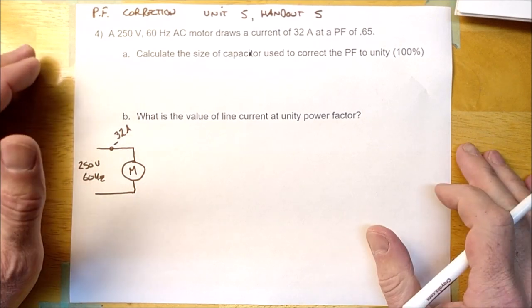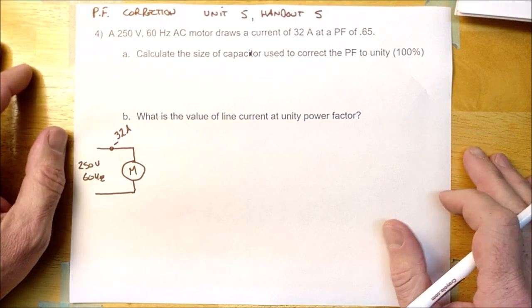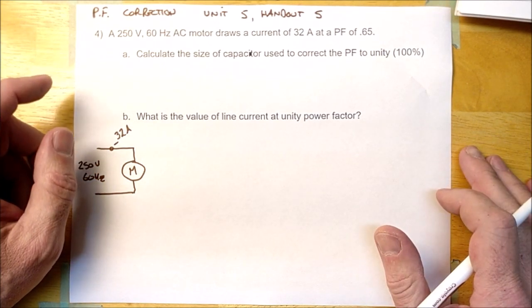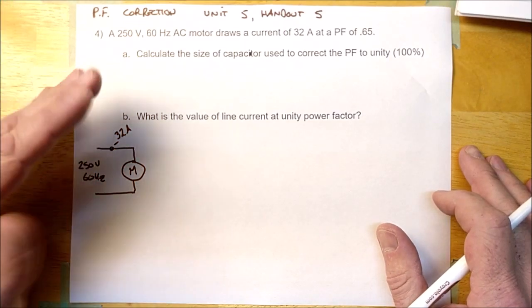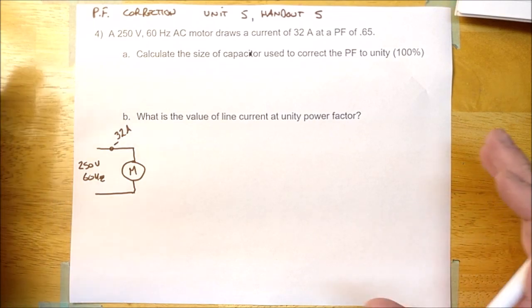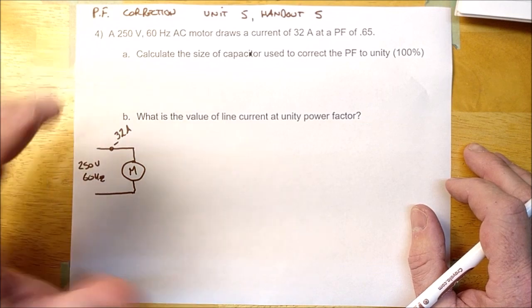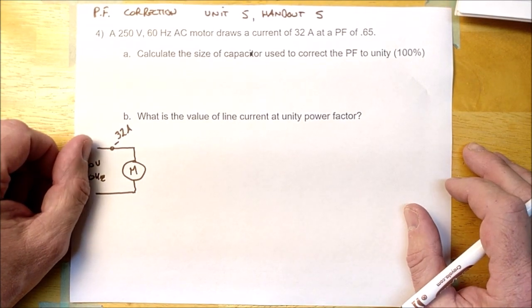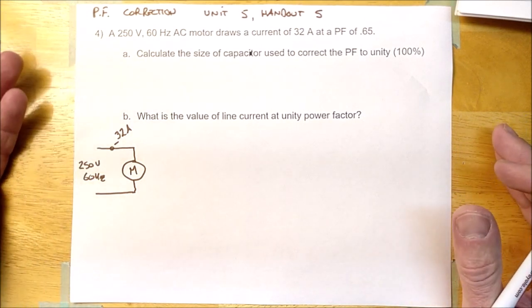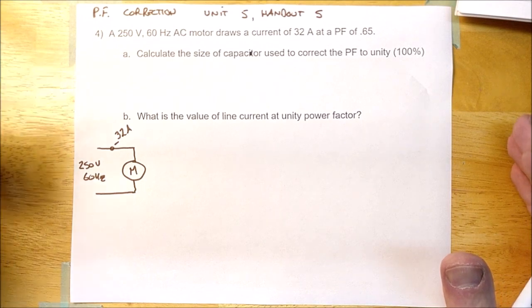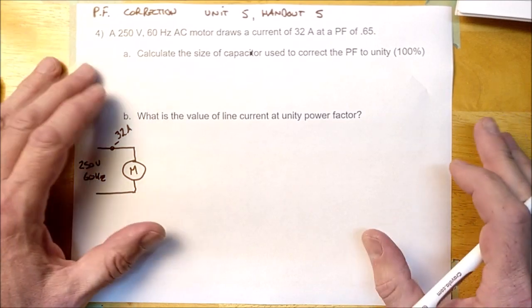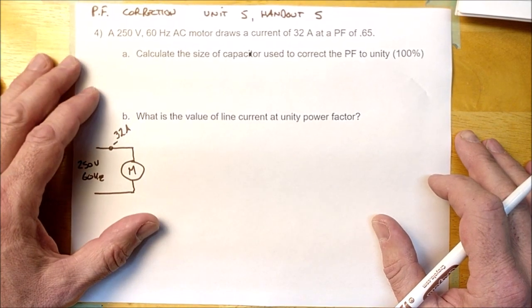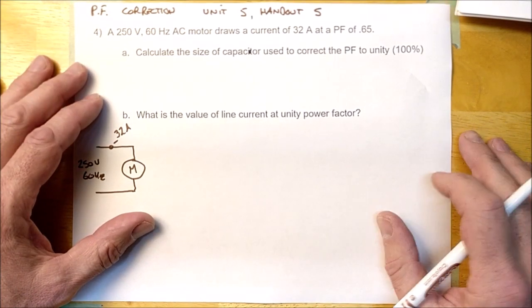Power factor correction is basically adding a capacitor — 99% of the time in parallel with loads — in order to improve the power factor. Because if you recall, there is true power and reactive power, and then there's the VA, which is the total power the circuit's using. It's the sum of the two powers. But your kilowatt-hour meter measures true power, and reactive power is ignored by the kilowatt-hour meter. That's really annoying to the supply authority — they just charge you for your true power.